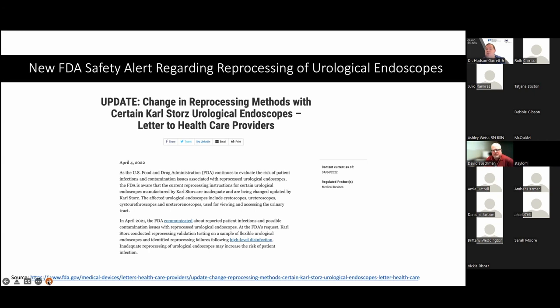This is the one I was referencing, where even if you follow the reprocessing steps as validated by the manufacturer, it's actually failing reprocessing. That tells us we had a fundamental regulatory failure here in assessing the risk of following the IFUs, those instructions for use, and ensuring that the device was going to be safe for patients.